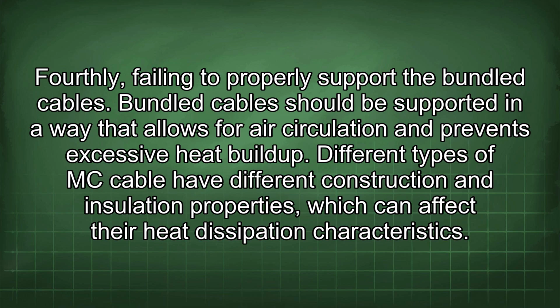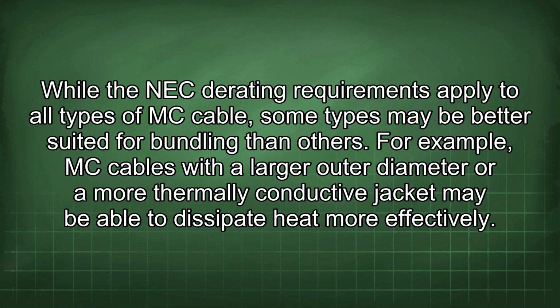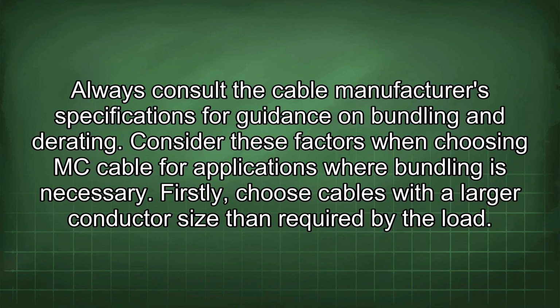Different types of MC cable have different construction and insulation properties, which can affect their heat dissipation characteristics. While the NEC derating requirements apply to all types of MC cable, some types may be better suited for bundling than others. For example, MC cables with a larger outer diameter or a more thermally conductive jacket may be able to dissipate heat more effectively. Always consult the cable manufacturer's specifications for guidance on bundling and derating.